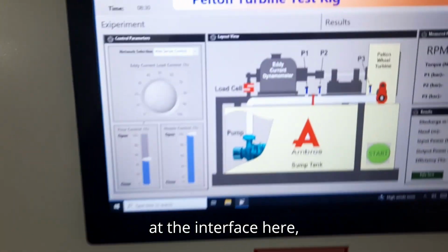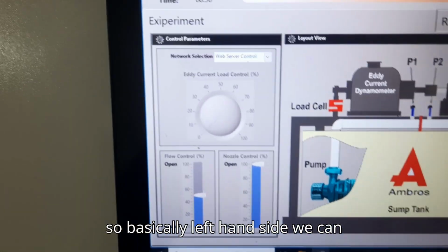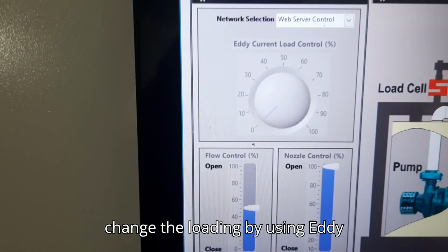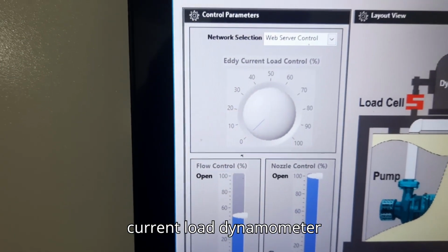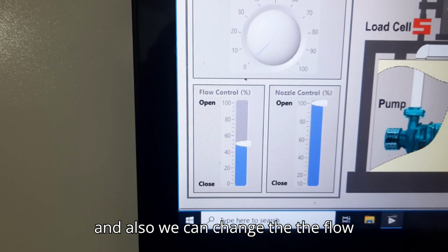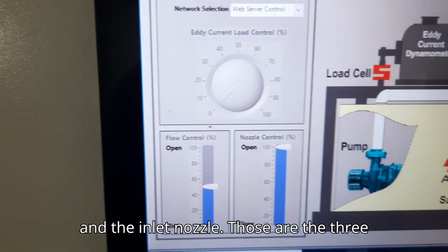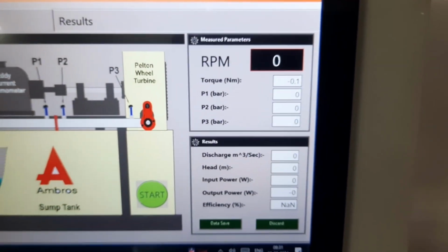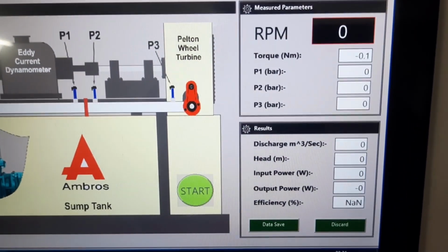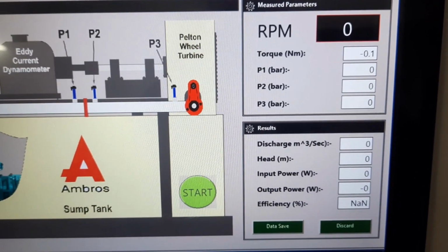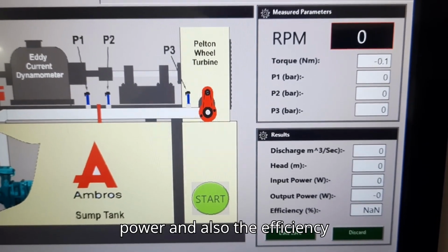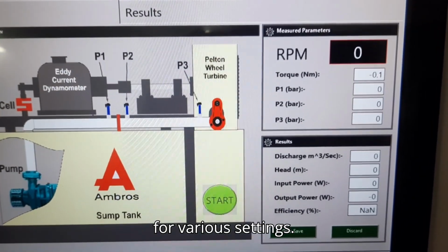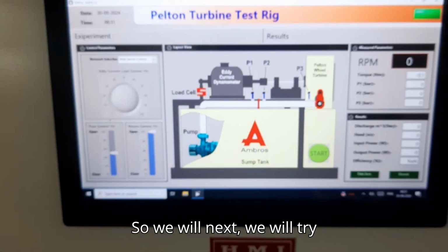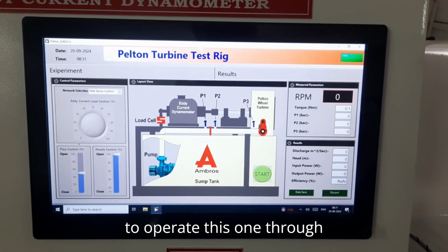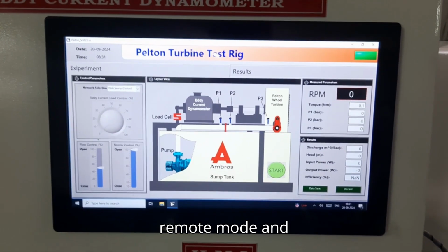So if you look at the interface here, basically on the left hand side we can change the loading by using the eddy current load dynamometer, and also we can change the flow and the inlet nozzle. Those are the three controllers available, and these are the main features of the machine. And we can detect RPM, torque, pressure values, discharge head, input power, output power, and also the efficiency for various settings.